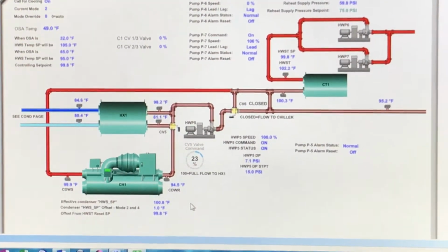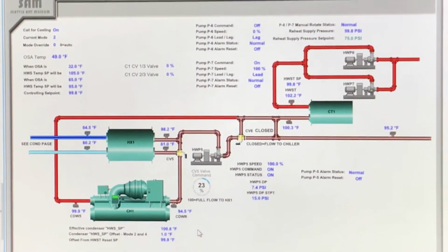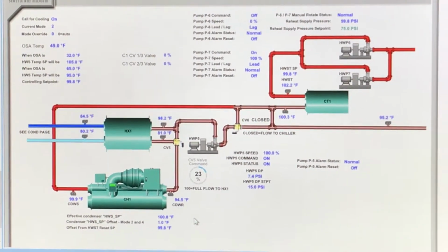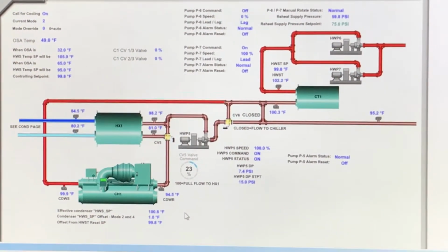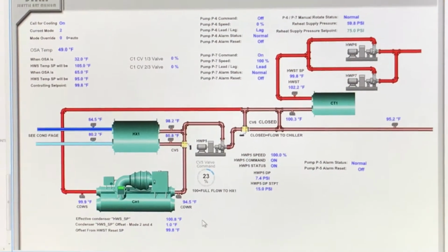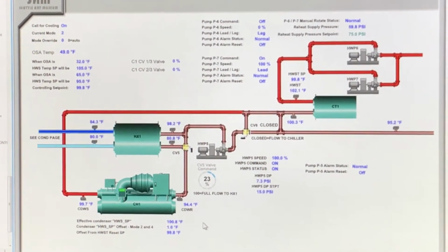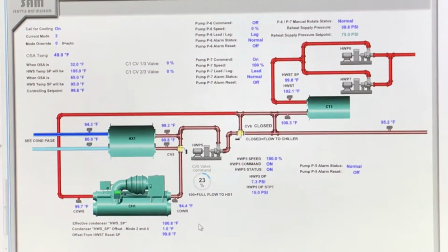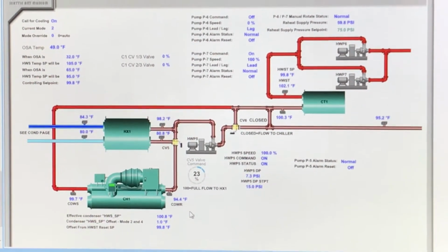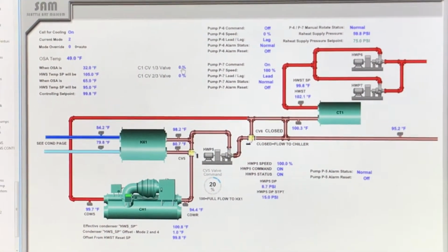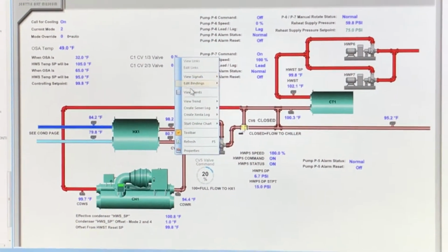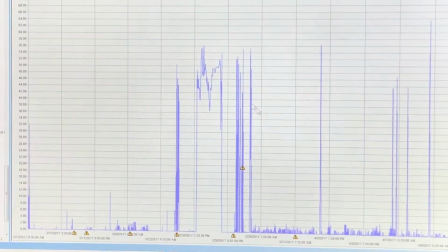We are kind of on the conservative side. You probably can move it to 2 and try that out. But I think I will look into that. And we looked at the log. It looks like it's doing really good right now with 105. With only a 1 degree offset, we're doing really good. Most of the time, on average over 10 days, the valve is 3% open. So it's pretty good.